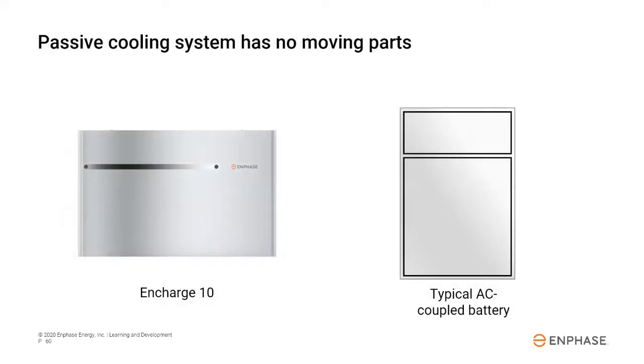Lithium-ion batteries generate heat when they charge or discharge, whether that's LFP or NMC. To keep the battery temperatures within a safe range, they have built-in cooling systems. Since Encharge batteries have a safe and stable lithium iron phosphate chemistry, the simple passive cooling system can be used. Convection draws cool air from below the battery and warm air exits the top. No moving parts are required for this system to work. So again, no moving parts means keeping the number of fail points in the system to an absolute minimum.